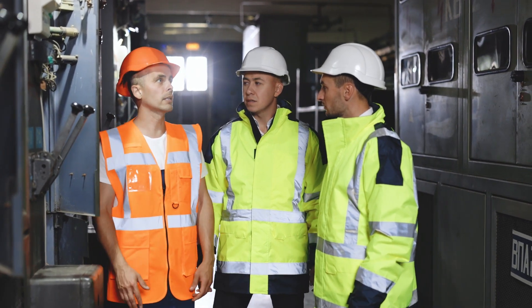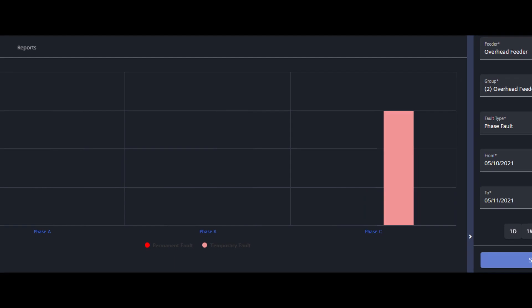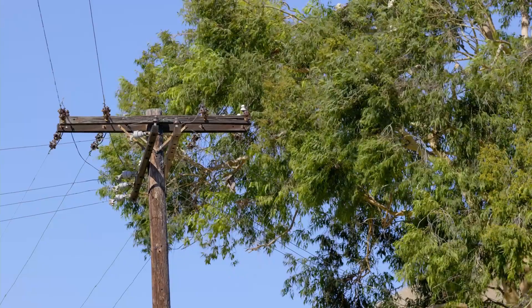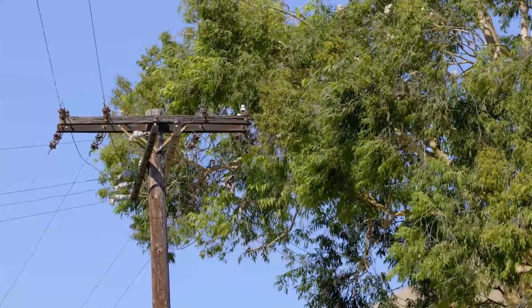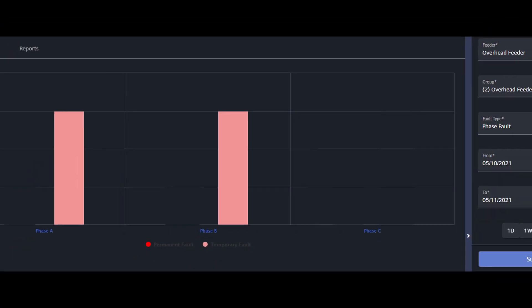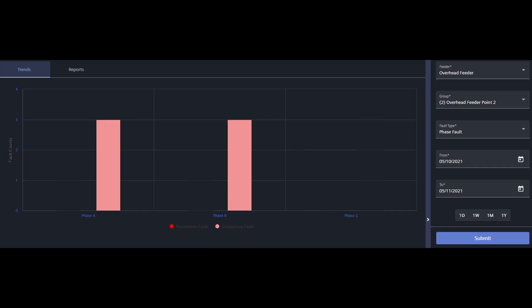See what the fault trends can show you. Several temporary faults only on phase C are typically caused by vegetation growing too close to the conductor. Or, as this chart shows, temporary faults on phase A and B at the same time can indicate that the conductors are swinging due to powerful wind, and a spacer can help to solve the situation.